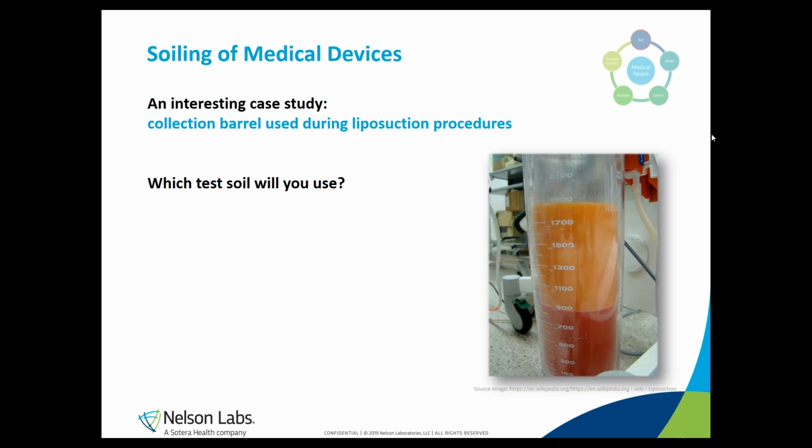Just to make this all a little bit less abstract, I have here a small case study. We got once a question from one of our sponsors to design a cleaning protocol for a collection barrel that was used during liposuction. And you can see an illustrative picture here on the slide, how it looks after use. So the first question was then, what can we use as a test soil? And we tried some different recipes here in our laboratory, but nothing looked really similar to what you see on this picture.